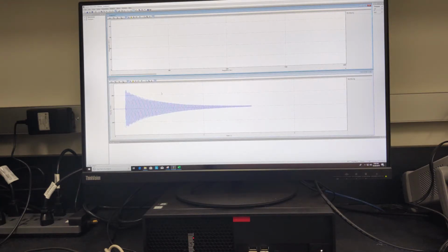As you can see, the new waveform is pretty smooth. The magnitude decreases logarithmically, and there is no big magnitude at the beginning of the cycles. And you also have a complete ringing down at the end. Also, check the beginning of the waveform. Make sure there's no vibration over there, which may be caused by the vibration of the environment. Now you can see the indicator of the trigger is on again, which means you can start another strike.